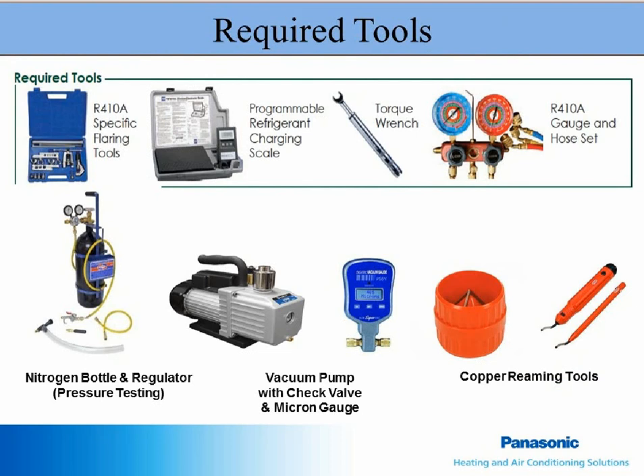All Panasonic systems use 410A refrigerant and require a few specialized tools. A flaring tool for a 410A system will make a flare with a slightly wider shoulder to help seal better. A flaring tool with an eccentric lobe and a clutch will also help make a quality leak-free flare. The use of a torque wrench will ensure that connections are not over or under tightened. Too loose will cause leaks, and too tight will cause copper or brass connections to split, which will also cause leaks. All Panasonic units have 5/16" service port connections, so a set of 410A gauges and hoses with 5/16 connections is needed. A 1/4" male to 5/16" female adapter could also be used.